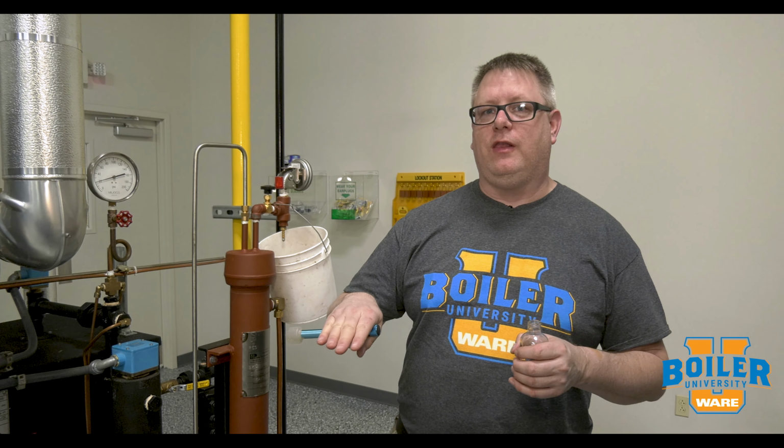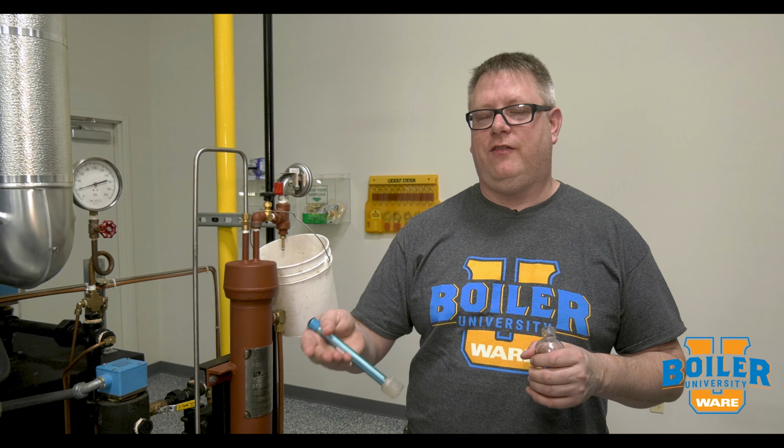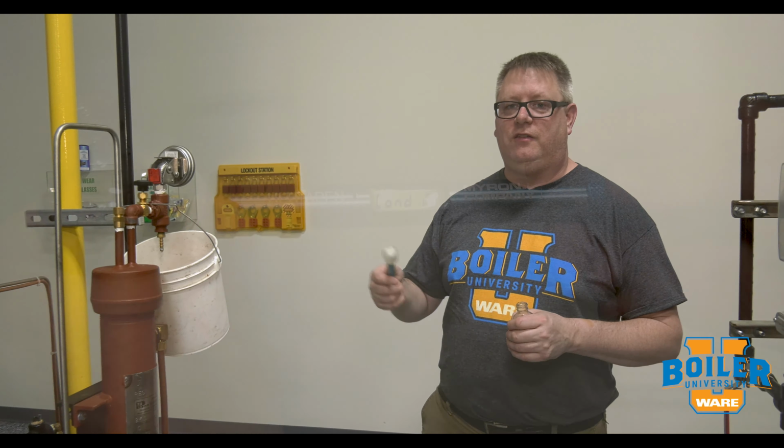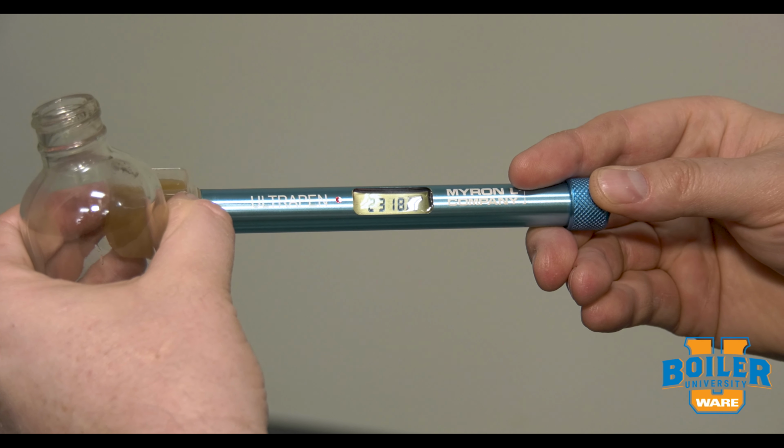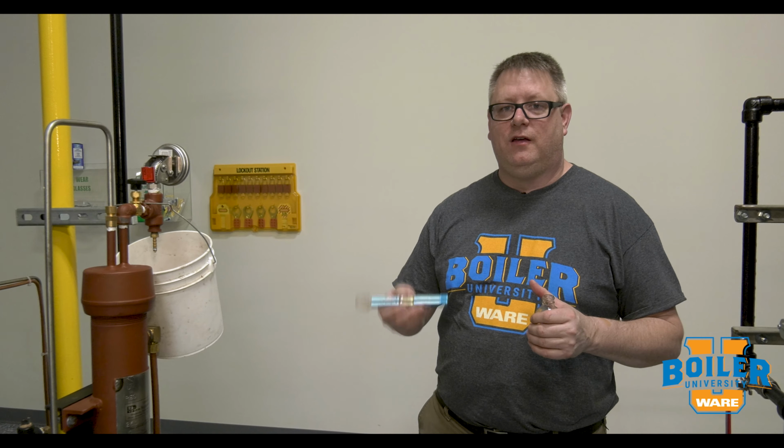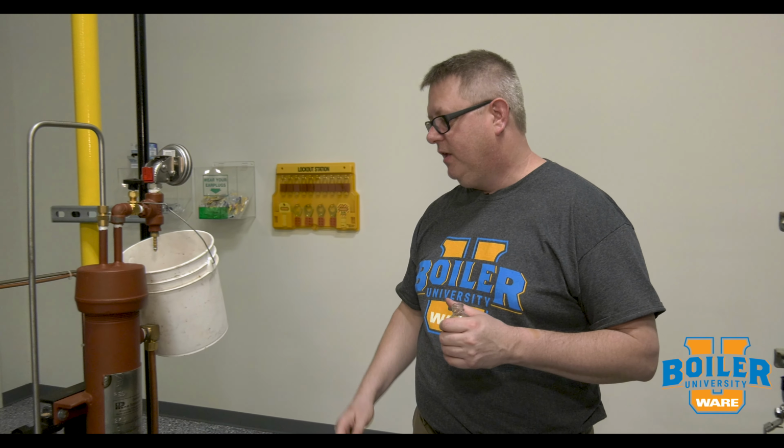The reason that water level behaves differently with different levels of conductivity is because the steam bubbles burst differently with normal and with high conductivity. With high conductivity, steam bubbles resist breaking, and so we get foaming and erratic water level behavior. Now, every boiler is going to be different, so what we want to do is be familiar with our water level behavior and do daily conductivity testing. And if we see anything out of the ordinary, go to the tester and get a good reading.